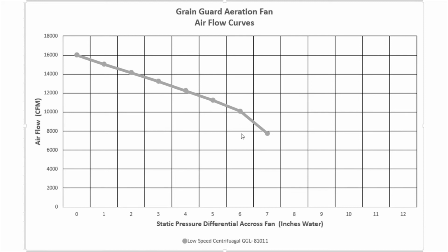But even with that, you really need to monitor your back pressure, because the danger with operating blind is that when you get close to this deadhead, your airflow drops off extremely. So you will literally get to no airflow if you are very much higher than this 7 inches of water.